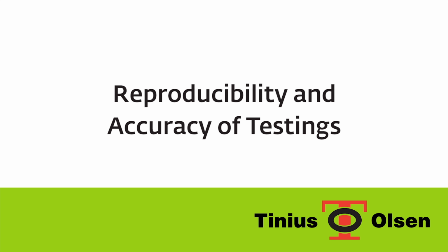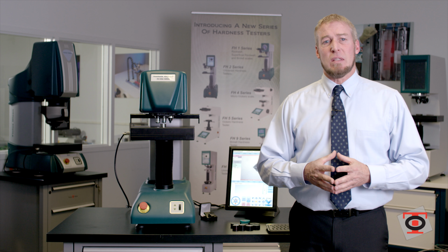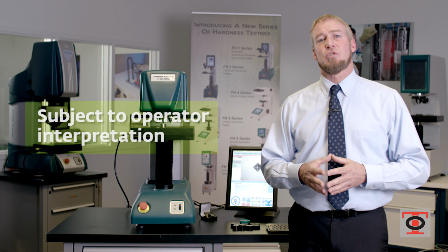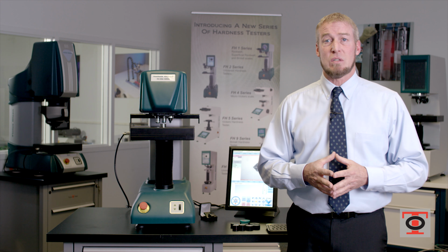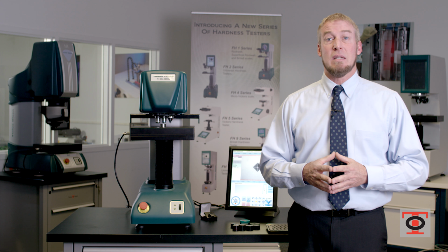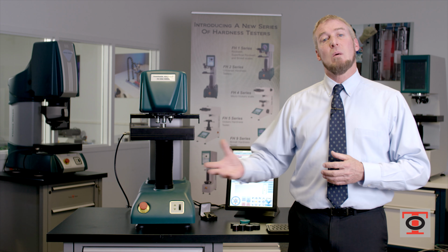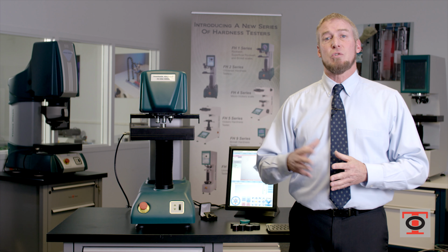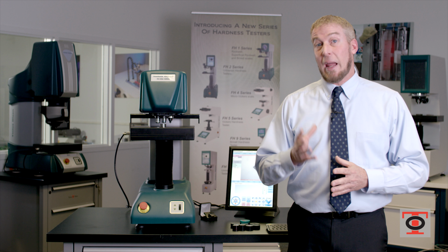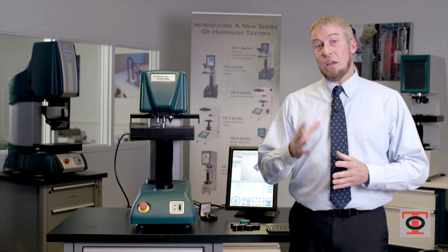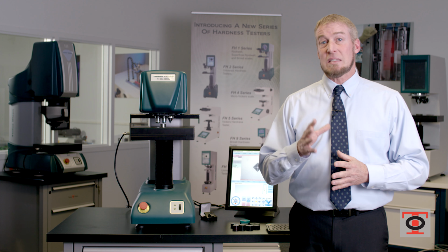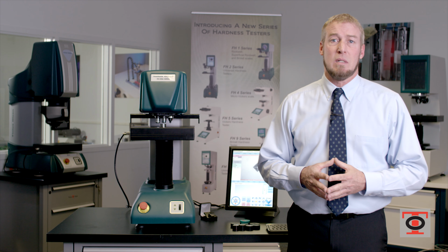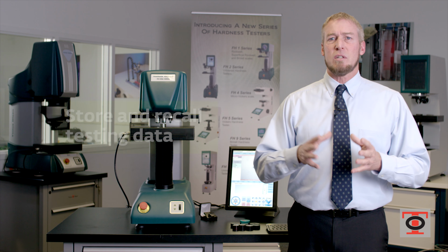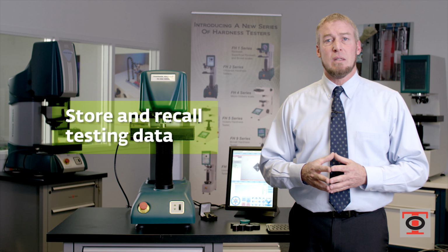So as far as reproducibility and accuracy of the tester, currently there's a lot of testing that's going on and the results are all subject to the operator's interpretation. You can have a very strong repeatability and predictability of the hardness tester because you have the ability of analyzing the indentations not only on the screen, but when you save them, if there's questions of the results, you can recall them with a picture and the measurement that was done that day, still having the ability to adjust that measurement and seeing where the measurement was taken within microns.